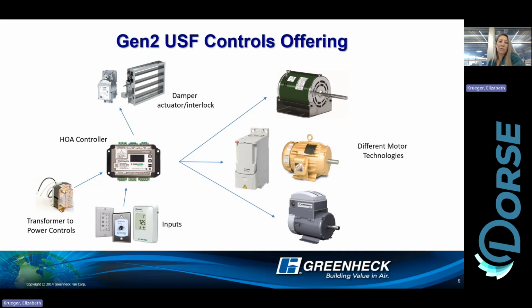That HOA controller there is so useful. Honestly, if you get your system set up with a VFD or you have an EC titanium motor, the interface for our HOA controllers, and maybe you can ask Chris for a better rundown on what that actually does, but really it's like a 12-page installation operation manual compared to the 200-page manual that normal VFDs go for. So it has a similar function to VFDs, just much, much easier to use.